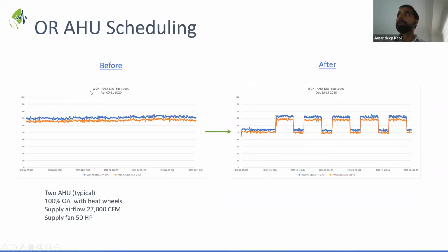Okay, so these are the results. On the left is the VFD trend from before: blue is your supply, orange is your return, and on the right are the trends for the same fan after the unoccupied schedules were implemented. You can see that previously the fans were running at around 73 VFD speed, and once the unoccupied mode was implemented, they went back to around 55 or so. So there was considerable savings from this project.